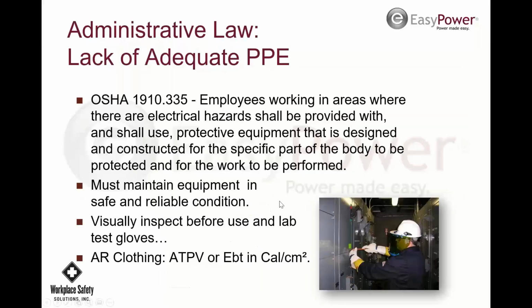Okay, 335, just as this is the PPE requirements. So OSHA doesn't have anything for general industry and construction other than utility standards about PPE, arc flash PPE. So we go by 1910.335, and that's what OSHA uses to cite arc flash PPE because it's worded very generically and very brilliantly by the director of OSHA who wrote this standard.